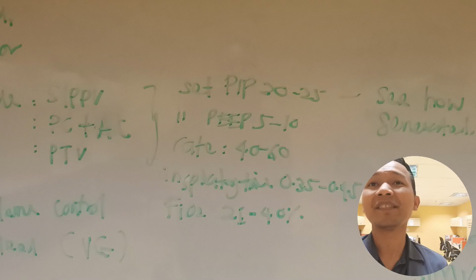Okay, but for PSV, pressure support ventilation, that one basically depends on the patient's inspiratory effort. It has nothing to do with the machine's set I time, but the machine only supports according to how much you set. If you set pressure 16, it will give 16, but this depends on the patient's I time.